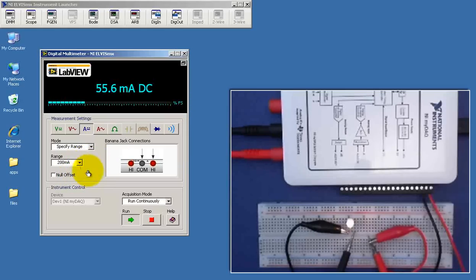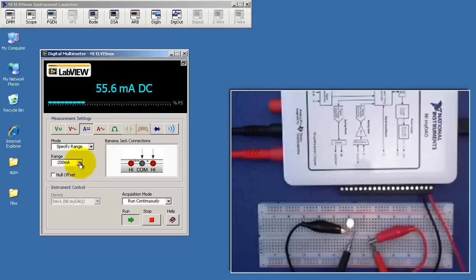Let's switch that to the 200 milliamp range. This gives us a little bit more accuracy, 55.6 milliamps.